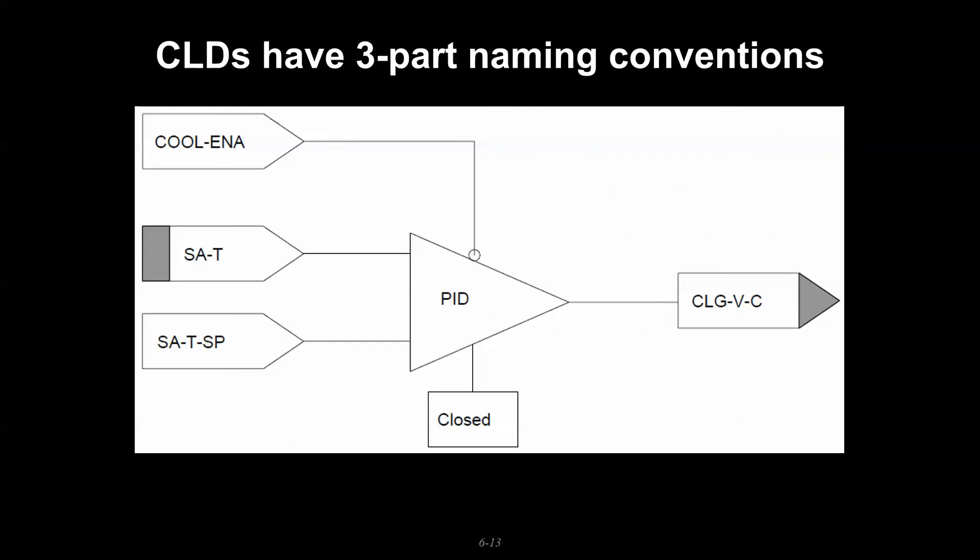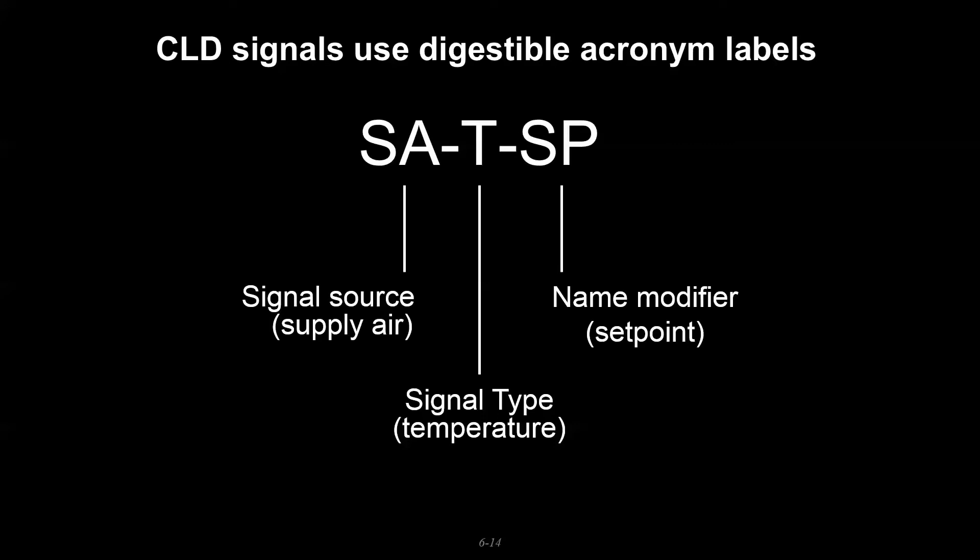Let's start with some convention so you can see some of these acronyms. The unified facility criteria and whole building design guide dictate some of the ordering of these acronyms in our control drawings. The first one is some type of signal source, like supply air. Second is the type of signal - if supply air is part of the air side system. Then the variable involved - whether we're looking at pressure, temperature, or humidity. In this case, T represents temperature. Finally we might have modifiers, which are optional. In this case we add the modifier to indicate that we're not looking at the supply air temperature itself, but the setpoint that we want that temperature to meet.